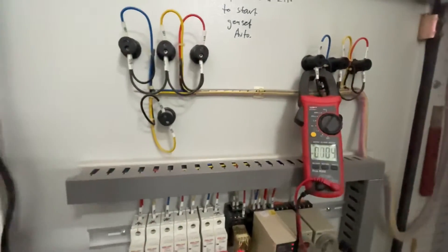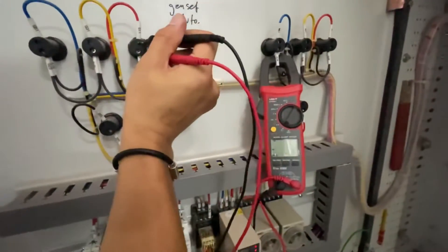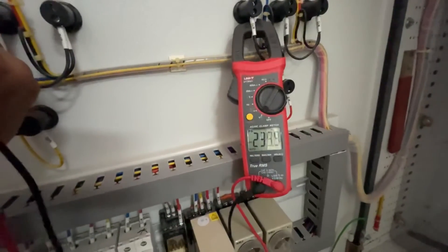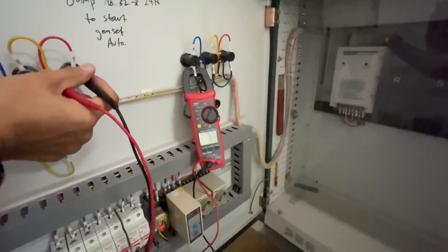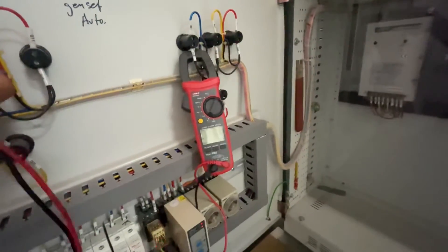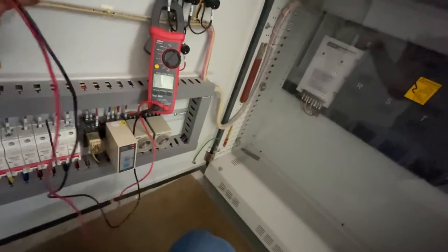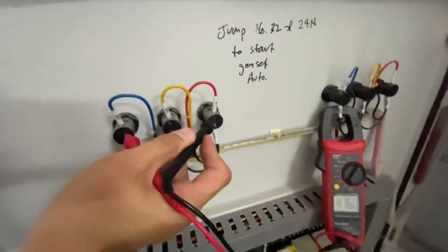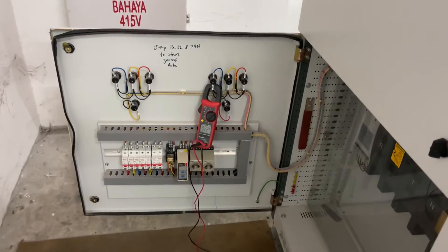Now let's check the voltage. For single phase, red, yellow, and blue are all around 240V. Then checking three phase: red-yellow is about 416V, yellow-blue is 416V, and red-blue is also 416V. There you have it — this is how we check the genset remotely from the ATS panel.